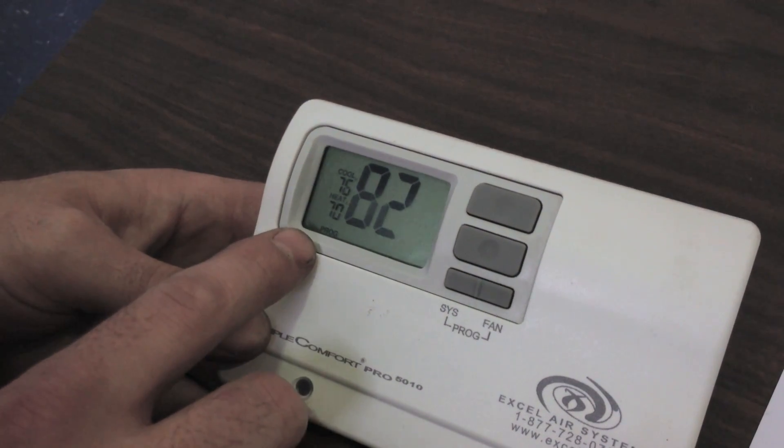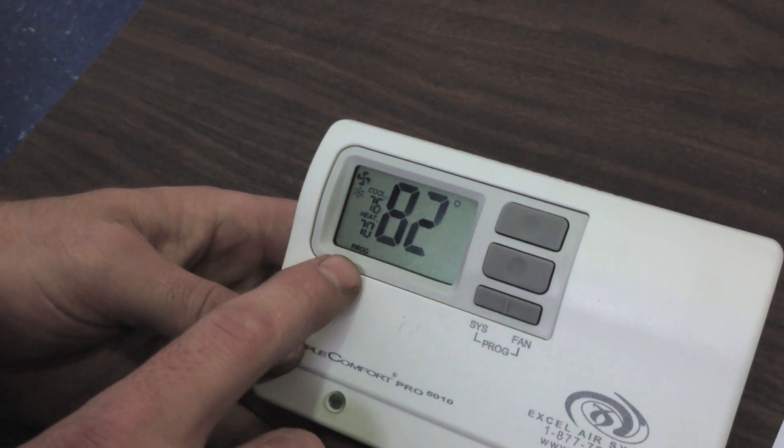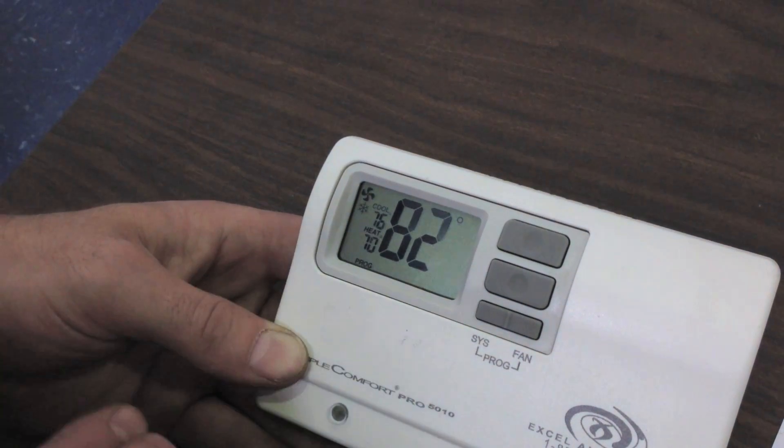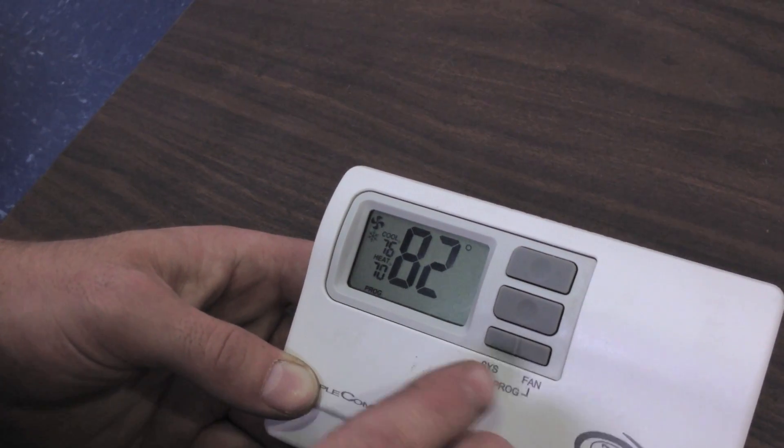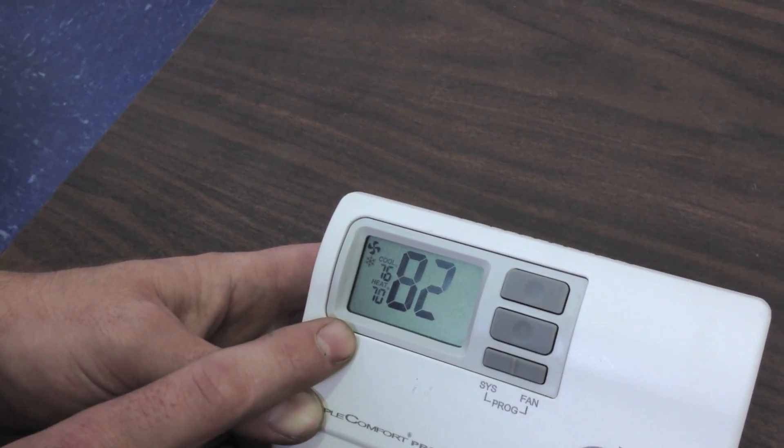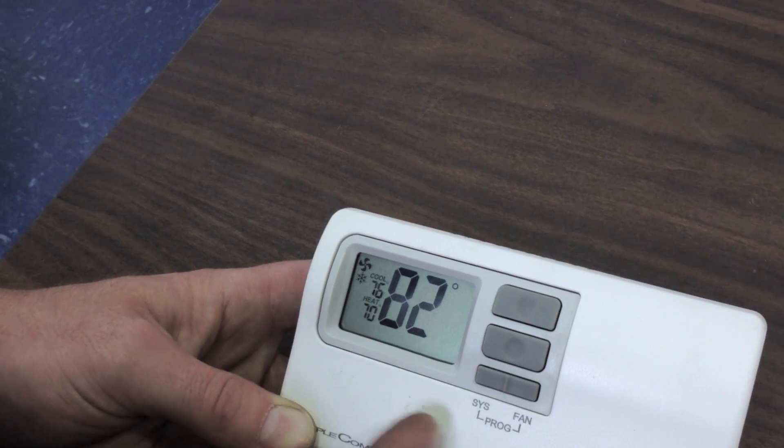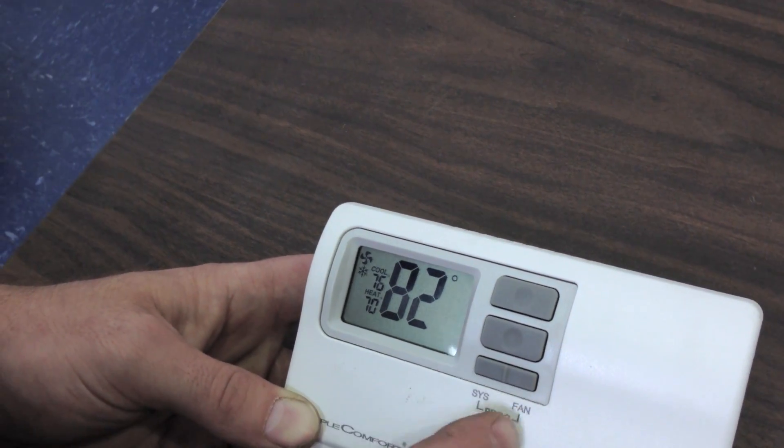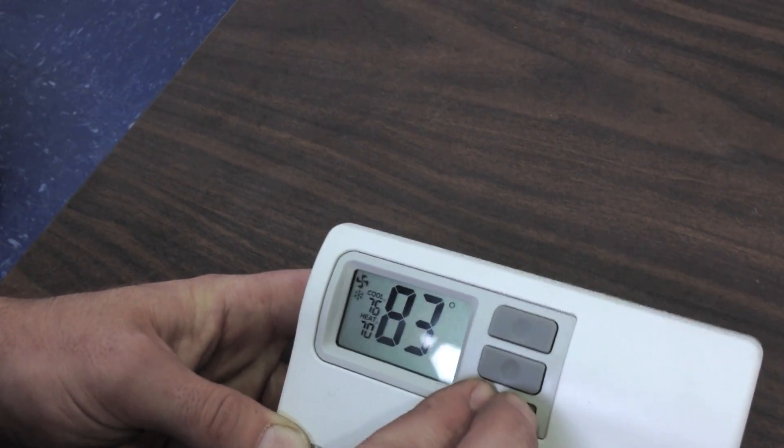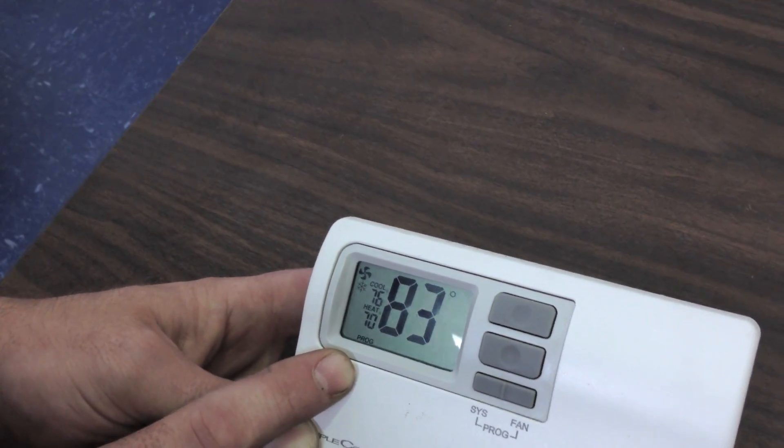And now notice we have P-R-O-G displaying in the bottom corner, meaning it's running our program. If that word is not there, you simply push the system and fan button one time at the same time. And the word P-R-O-G disappears. And now it is a regular manual thermostat. To reinstate your program, push system and fan at the same time just for one second. And the word P-R-O-G reappears. And your program will again run.